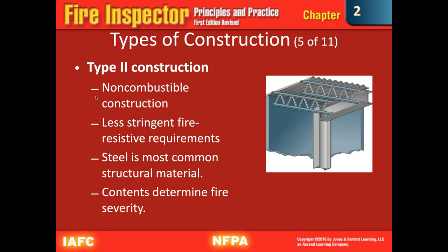So this is a type two slide. This last comment down here kind of drives home what I was saying about the stuff inside of them will burn. What's inside determines the fire severity. If you're a type two building, but there's a place in Poplarville out on 26 where all they sell is gypsum board and bricks and stuff like that, that's really not that big of a deal, right? That stuff's not going to burn any better than the building does. But if you're a furniture store, then that's obviously a much higher fire severity, not because of the building, but because of what's inside of it.